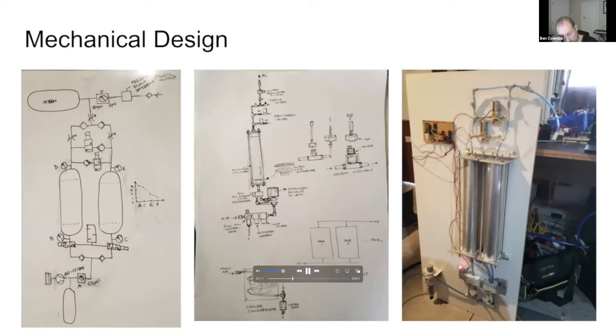OX uses a pressure swing adsorption process, which is a simple and proven design. The two tanks are filled with 0.5 millimeter synthetic zeolite balls with a very high surface area to create a molecular sieve. When pressurized room air is passed through the sieves, the nitrogen is preferentially attracted to the zeolite, which is known as adsorption. This allows the oxygen and argon to filter through.